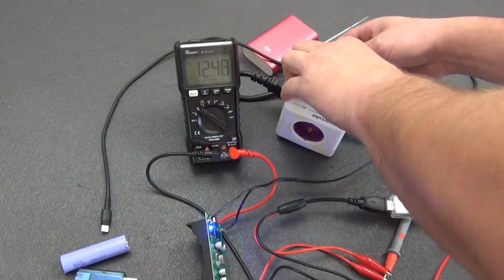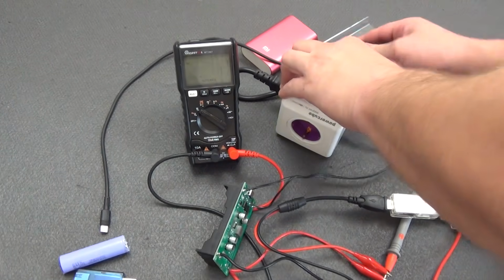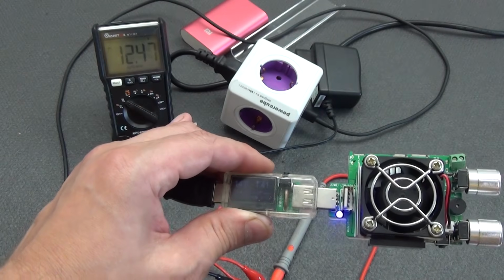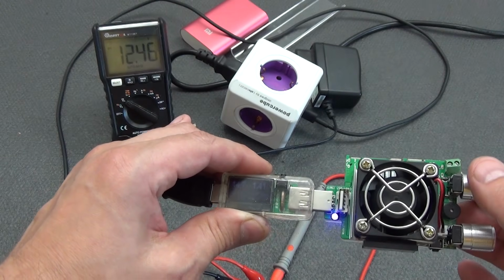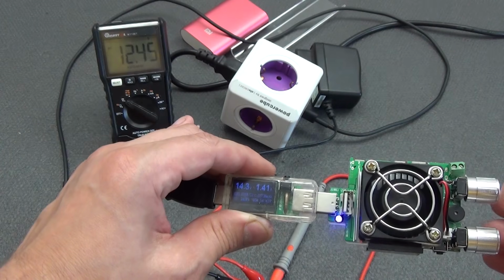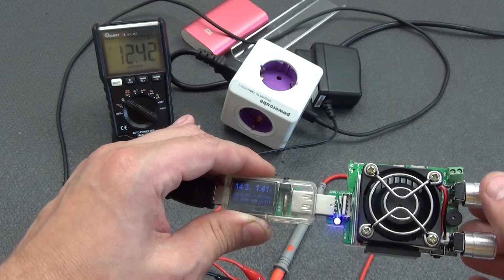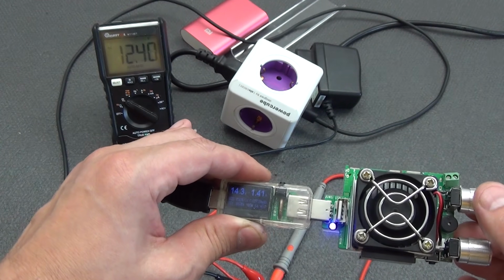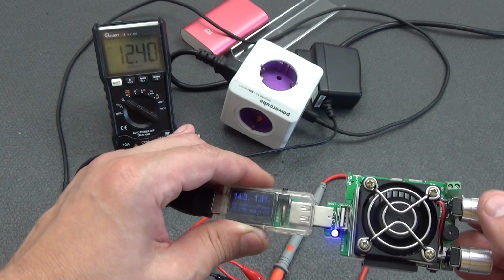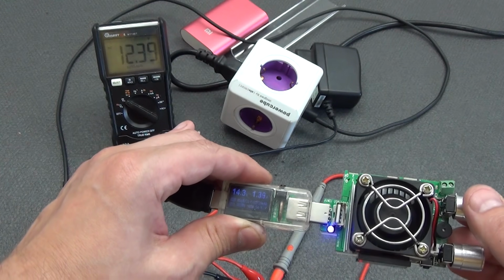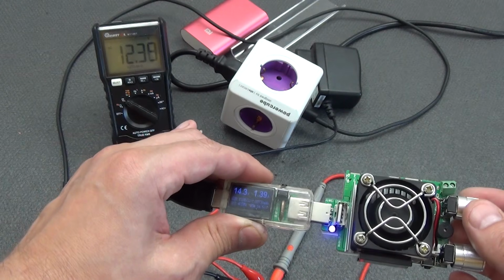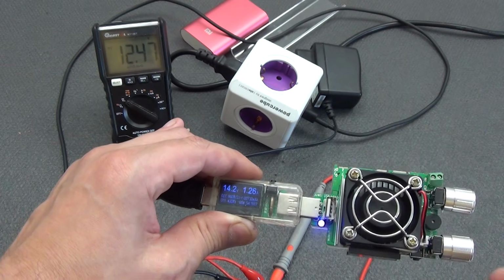Now we turn off the external power supply and leave the UPS running only on batteries. The maximum current with such a connection is 1.3 amperes. But as soon as the current increases to 1.4 amperes or higher, the UPS begins to go into protection. At the same time, the output voltage drops several times and recovers, which confirms the activation of overload protection.